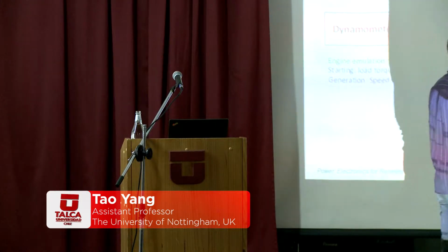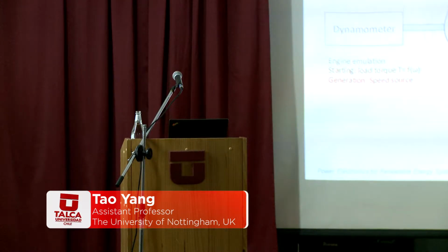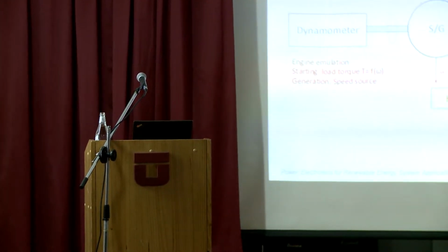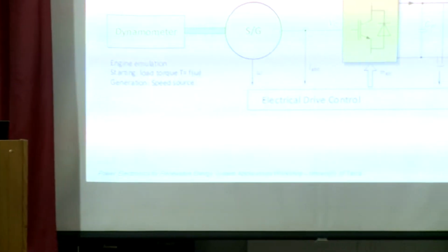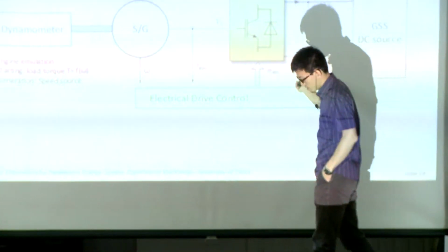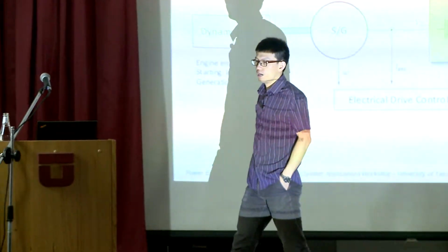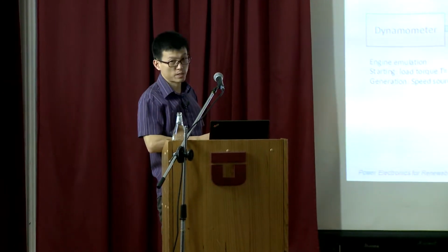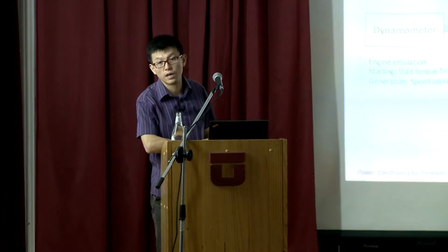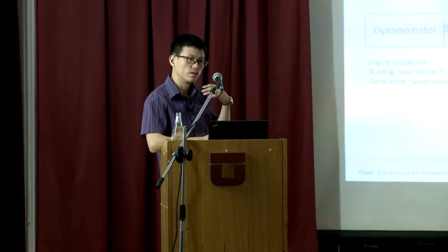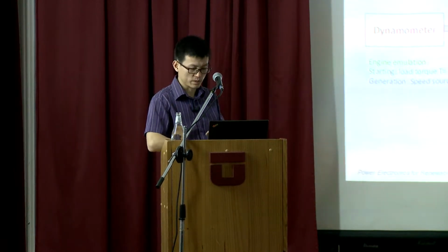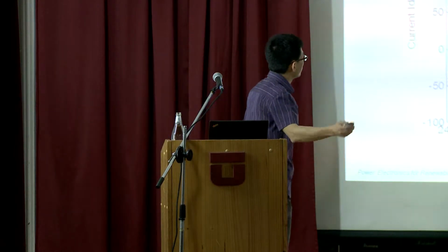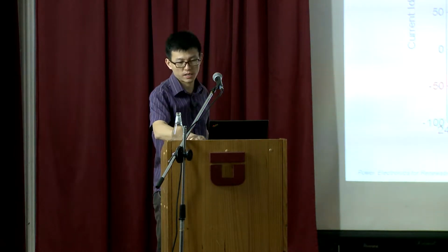Essentially, we manipulate the voltage here because it's only one system. We don't have multiple sources on this test rig yet. In the very beginning, we tested this droop concept using a standalone system. We just manipulate the voltage here to see if the droop really works in this standalone concept. And these are the results we got. Let me scale up a bit.